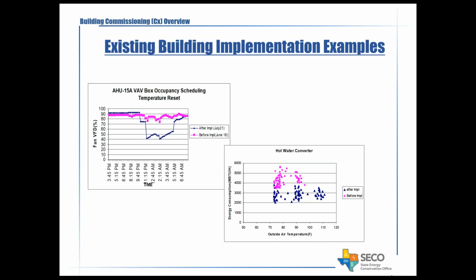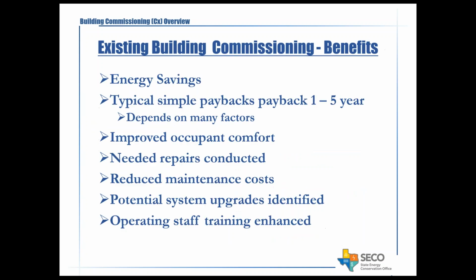Another important thing in existing building commissioning is that you must see how things were running before, and document how things are running now. This could be done in new construction too, but it's more prevalent and important in existing buildings, where you show the differences from any sequence changes and how they impacted operations. These are good examples where, as a result, less energy will be used. Presenting this information in the final commissioning report is important in existing building commissioning.